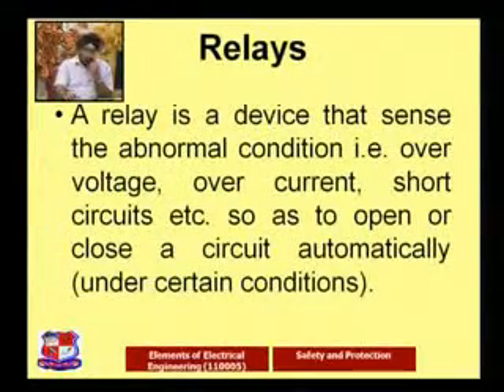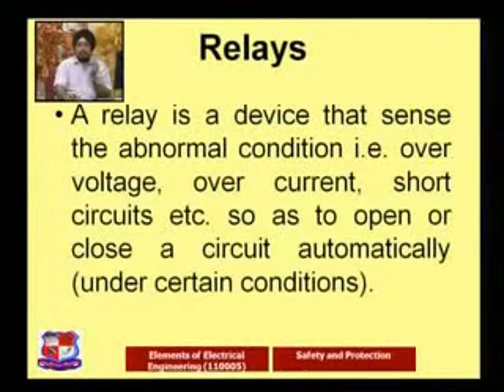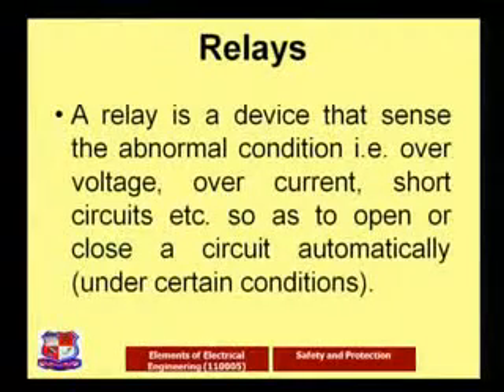We talk about fuses, MCBs, ELCBs, but actually the relay is one of the major components which plays the vital role in detecting all these things, because the relay is actually the sensing device. Until we sense that fault and the signal is passed to all these devices, they are almost useless. So for efficient use, the relay provides this, senses that some abnormal conditions are there, and gives tripping signals to all these equipments, so they can operate and work properly.